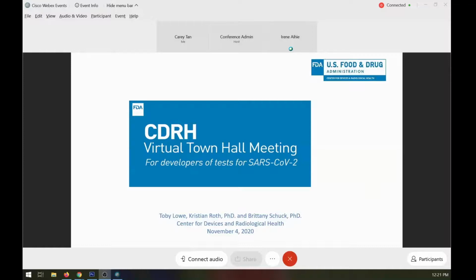My name is Roberta Bastion, from Tempest Labs. Just a question: if you have a test authorized under an EUA and you receive a false positive, are you required to report that via the MDR process? We would expect false positives to be reported both to the EUA holder, and it sounds like you are the EUA holder, and to FDA. So you could send that in through the MDR process or through the EUA reporting mailbox that should be on your letter of authorization. Thank you very much. Sure.